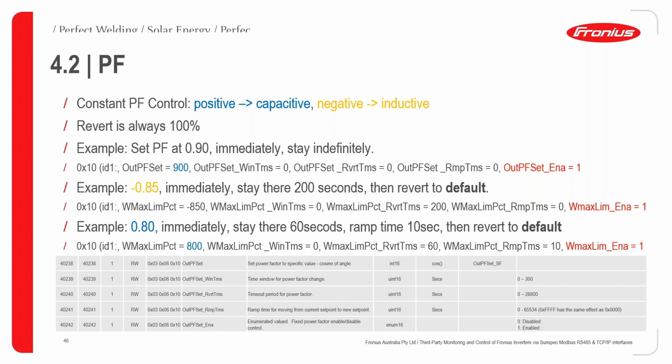And when control lapses, if it does happen or you disable the mode, then it will always refer to the default power factor setting at the moment, whether that's going to be a volt-var kicking in, or whether it's going to be power factor of 1 if it's not set. That will be the default, will always be the case.